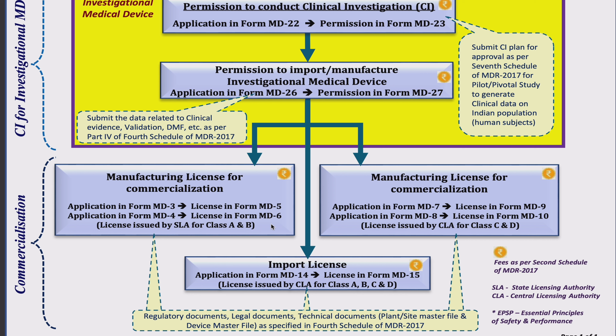For Class C and D manufacturing license, I need to apply in form MD7, and the CLA — Central Licensing Authority — is going to issue the license in form MD9. In the case of import for Class C and D, I need to apply in form MD8, and CLA will issue in form MD10. Please note that CLA controls the import license regulation for all kinds of medical devices — Class A, B, C, or D — and for import license, I need to file MD14, and CLA will issue in form MD15.